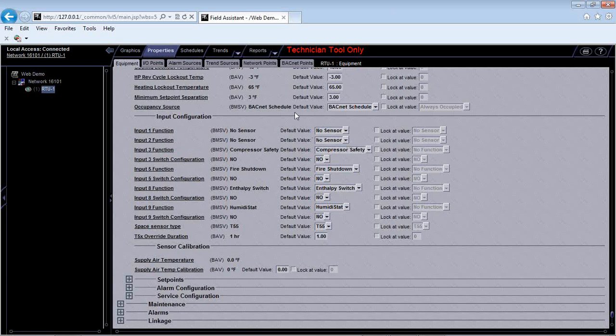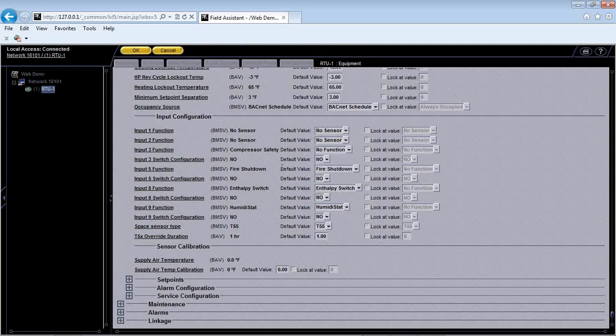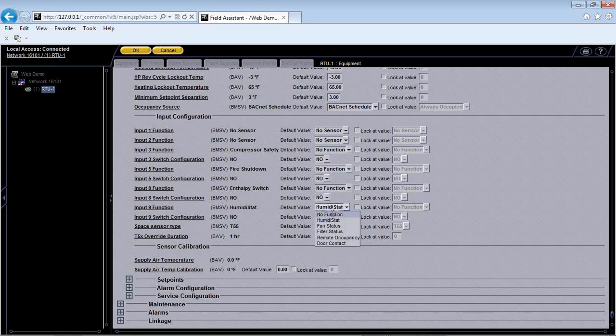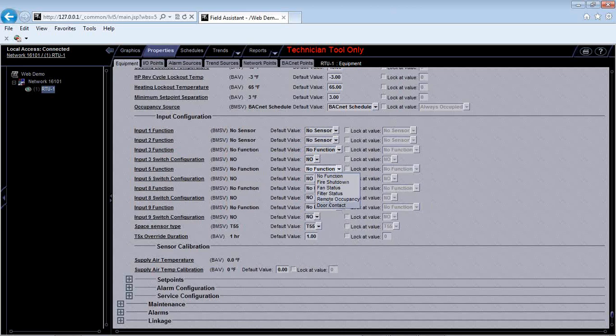So I need to tell it, hey, I don't have a compressor safety, or I don't have fire shutdown wired in. It doesn't know. It thinks it has it. So what I'm going to do is, if I hit this drop down, I'm going to hit no function for input 3 because I don't have anything wired into it now. And I don't have fire shutdown wired in, and I don't have enthalpy switch or humidistat. But you can look at the different options of what you have: fire shutdown, fan status, filter status, remote occupancy, or door contact.